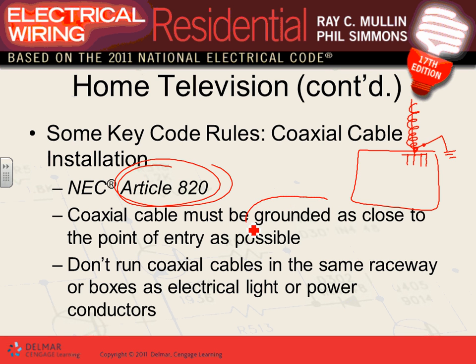So that's the grounded part of it, required by the code. Do not run the coaxial cable in the same raceway, boxes, or cables with lights and power. This applies to all low voltage systems: security, phone, data. We cannot put them in the same box or cable unless they're listed for it, or the same conduits used to distribute signals through the building. When designing a building, you'll see conduits dedicated to the fire alarm system and conduits dedicated to power and lighting. Sometimes fire alarm even gets its own dedicated conduit, separate from the security system.